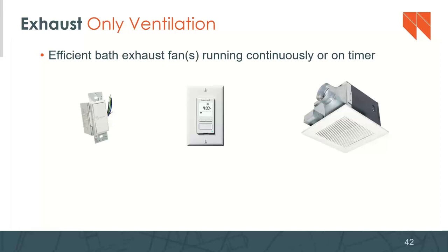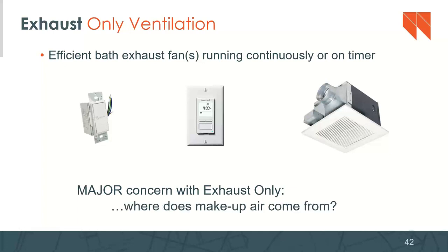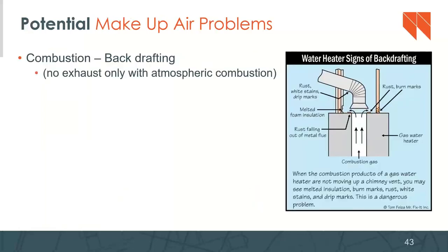All right, we'll talk about these in order. Exhaust only first. This is usually going to use an efficient bath fan running continuously or on a timer, as I've said. So this is a smart controller. This is another version of a smart controller. Looks like maybe we've got some programmability in there. And then of course the bath fan itself. Major concern with exhaust only: where does the makeup air come from? Well, it comes from somewhere. When you combine exhaust only with combustion appliances, there's a possibility for backdrafting.